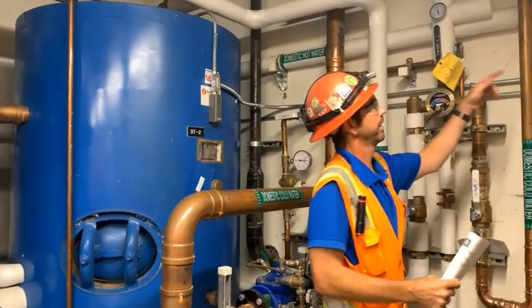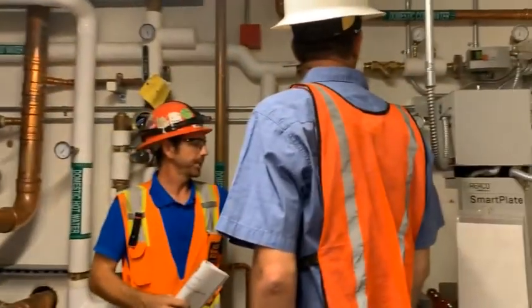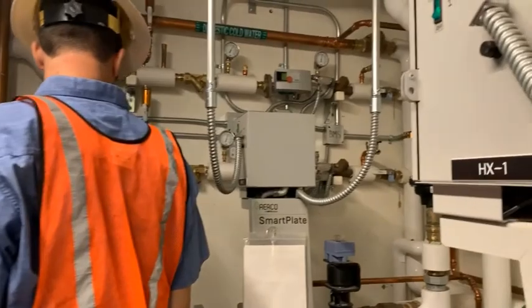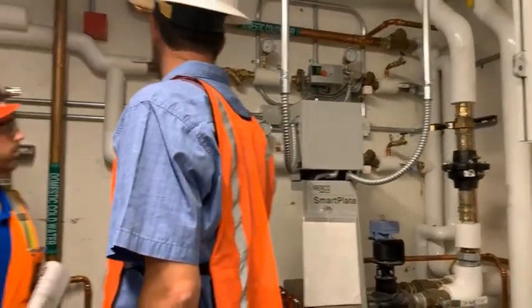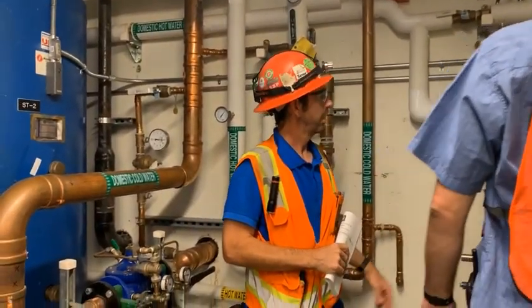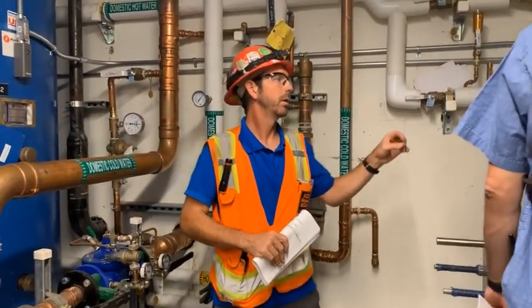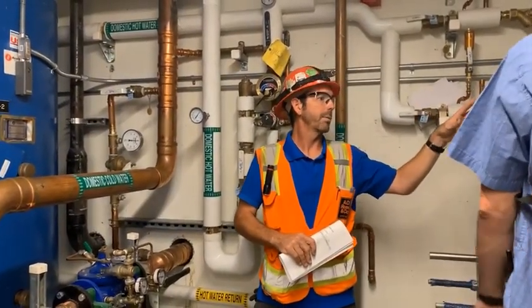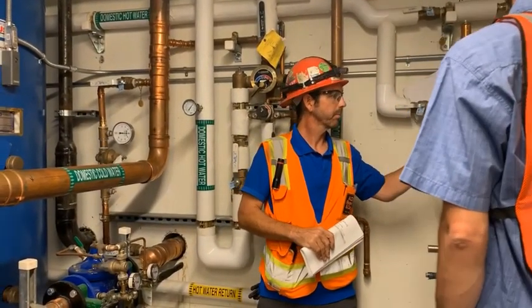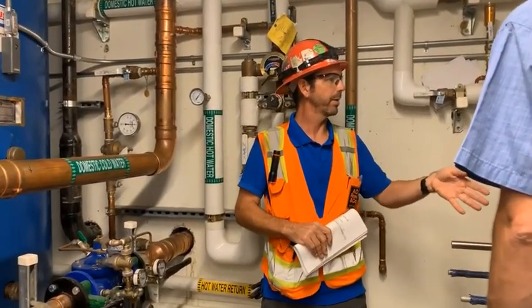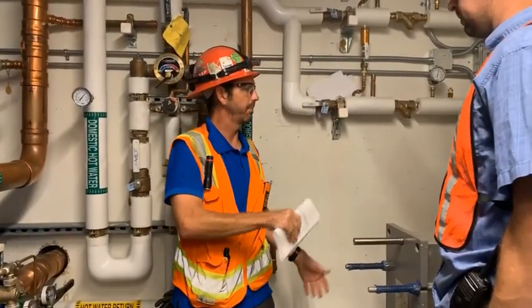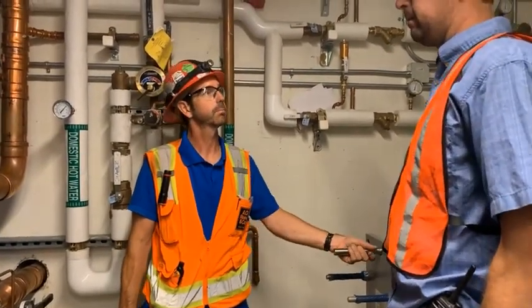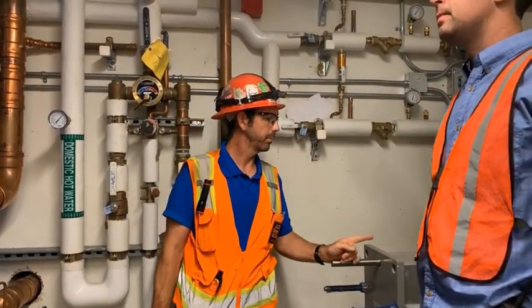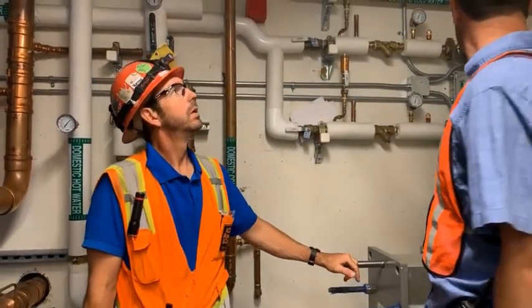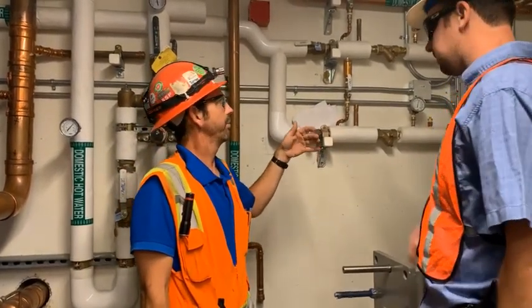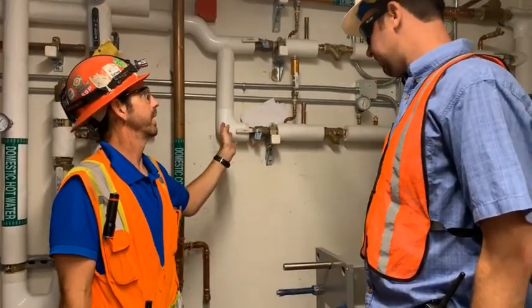And it'll draw water out of the tanks, push water through the heat exchangers right here, and then back into the tanks. Again, 140 degree set point. We'll talk about the heat exchangers tomorrow as well. We have domestic hot water and heating hot water system. The heating hot water is what's heating up the domestic hot water to 140. Okay? We'll talk about more of these tomorrow. Every piece of equipment has a shutoff, most every piece of equipment has the shutoff valve on the in and the out.